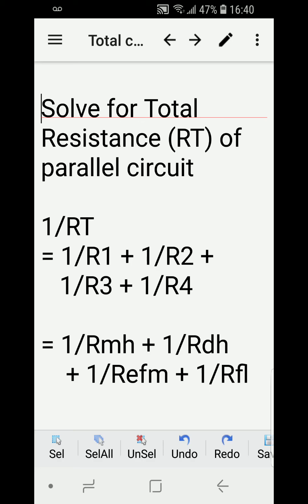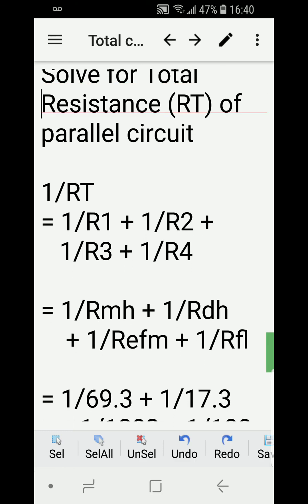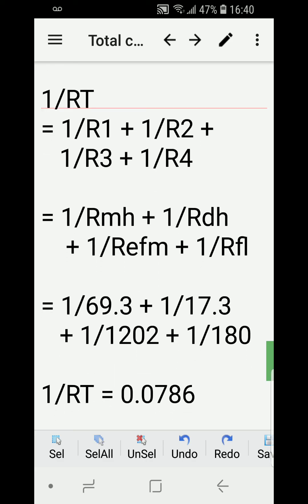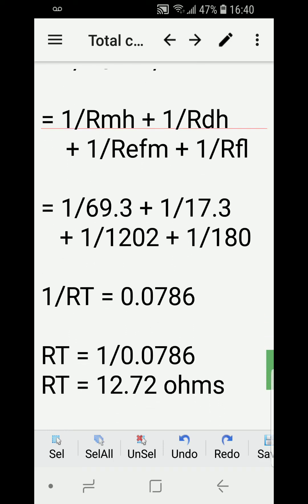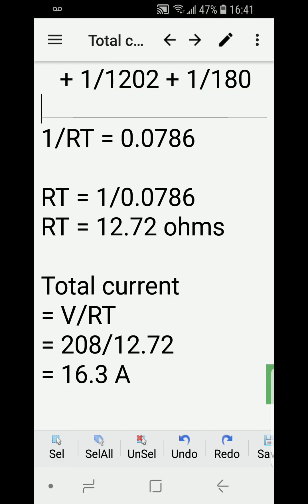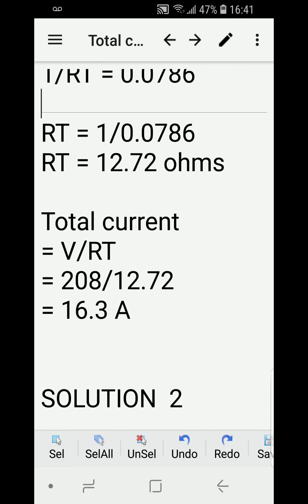Now we solve for the total resistance of the whole parallel circuit. The generic formula is: 1 over R_total equals the sum of the reciprocals of the individual resistances. So 1 over RT equals 1 over R_mullion heater, plus 1 over R_defrost heaters, plus 1 over R_evaporator fan motors, plus 1 over R_fluorescent lights. Substituting the calculated values, we get 1 over RT equals 0.0786, giving a total resistance of 12.72 ohms.